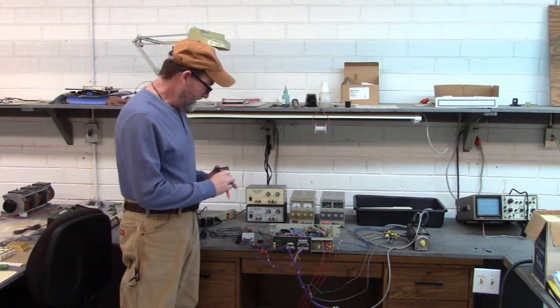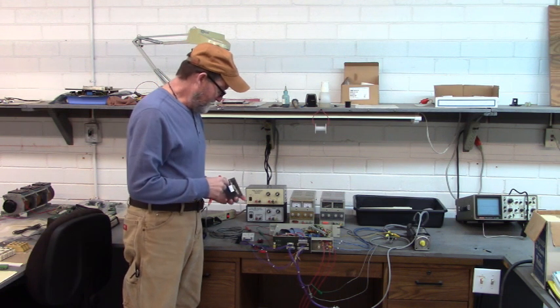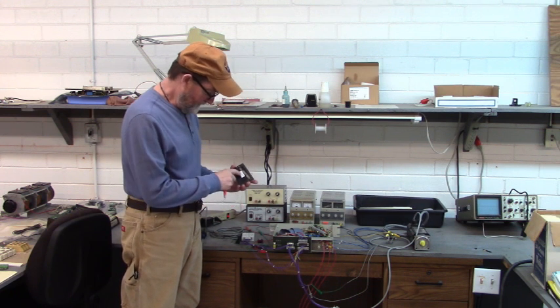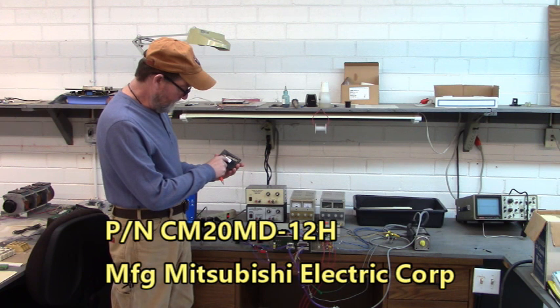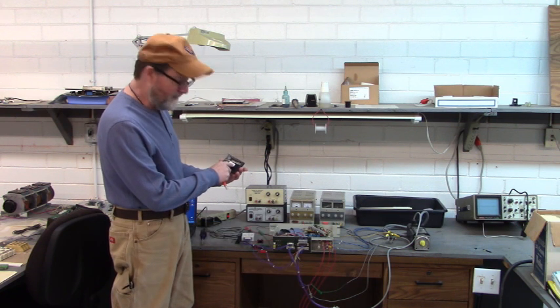The IGBT exploded on the servo drive. I replaced it and we're going to test the new IGBT in a little bit. Here's the old one — it's made by Mitsubishi Electric. Its part number is CM20MD-12H.